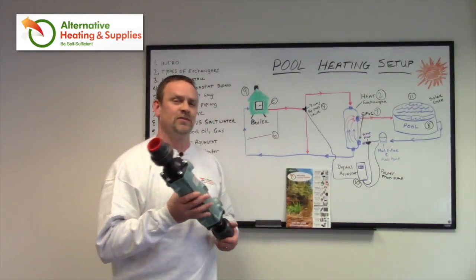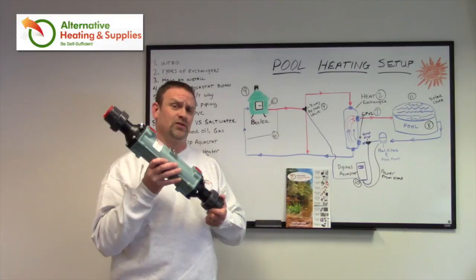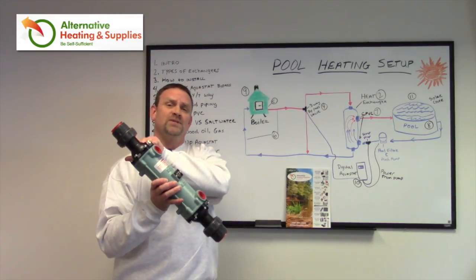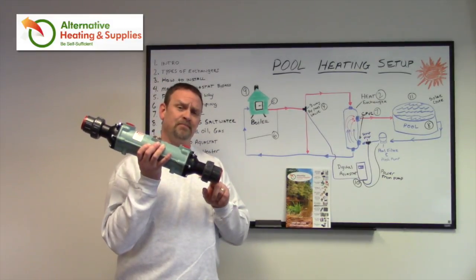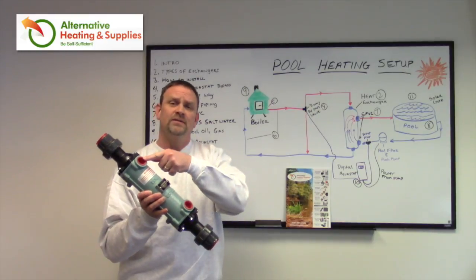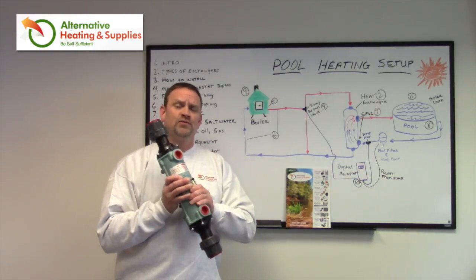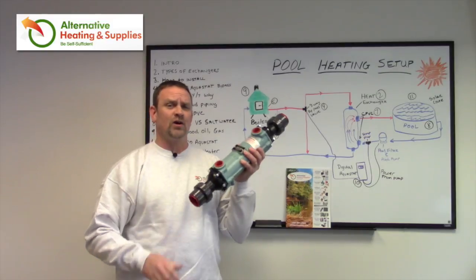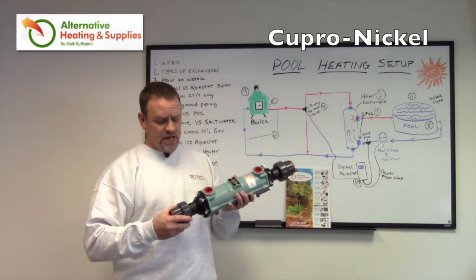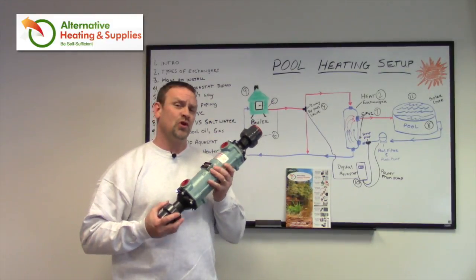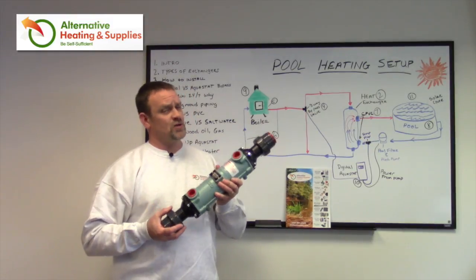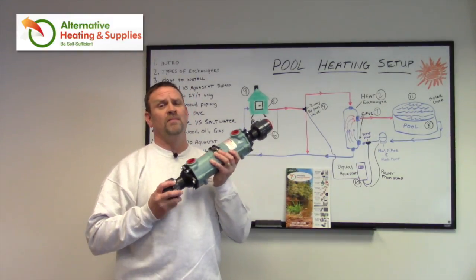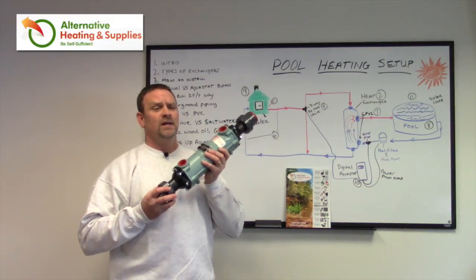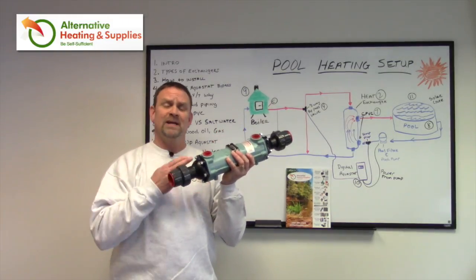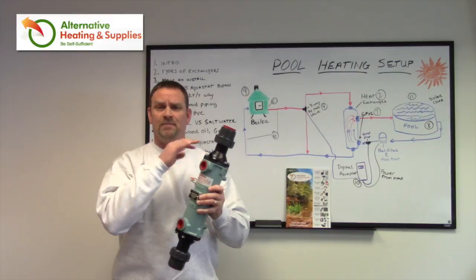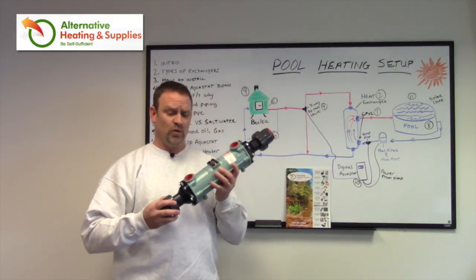There's another heat exchanger, which is also a tube and shell design. The pool water comes in at the top this time and out the bottom. The boiler water goes in the sides, okay? The difference with this one is what they call a copper nickel. Copper nickel is capable of handling saltwater pools. It can also handle chlorine. It is also a much higher grade heat exchanger. It has the capability of being cleaned. You can take off the top and bottom and get to the fingers that go through the whole heat exchanger.